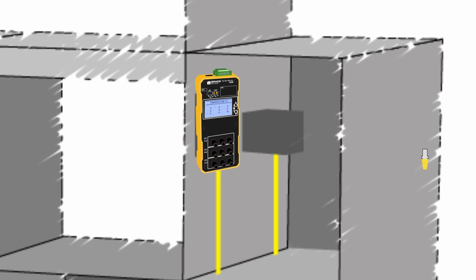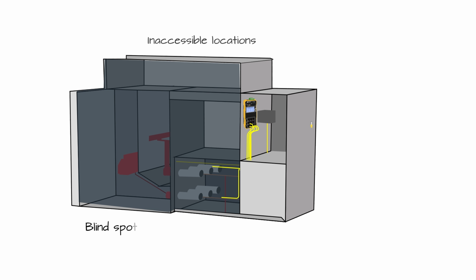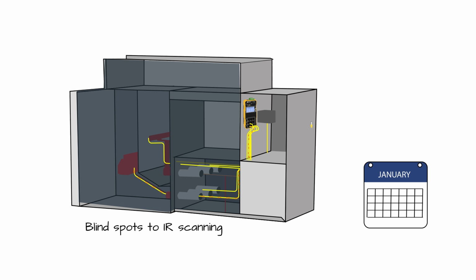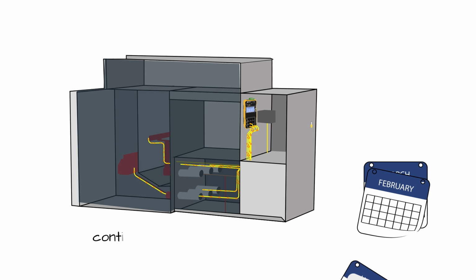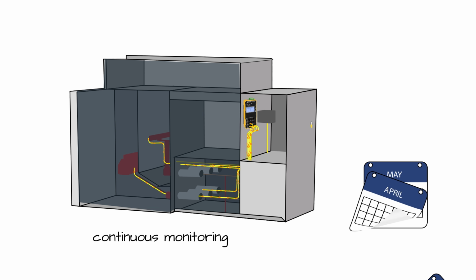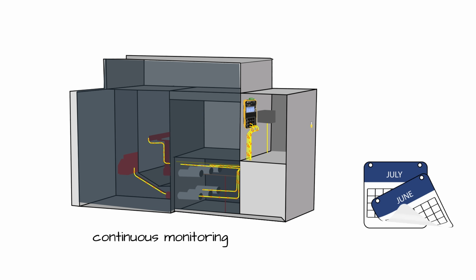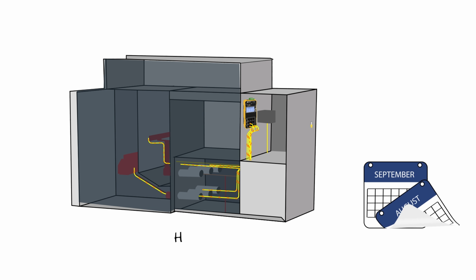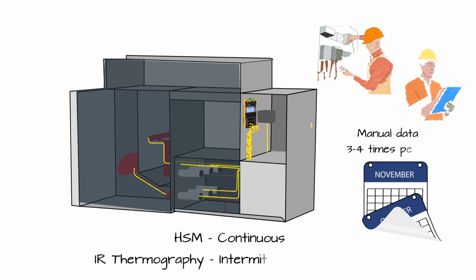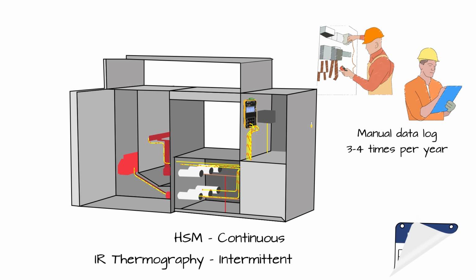Sources of heat may include inaccessible equipment and blind spots to IR scanning. The most obvious benefits of the HSM over IR thermography come from the continuous real-time monitoring feature. In addition, the successfully proven measurement accuracy of the probes is not subject to calibration errors, as can be the case with IR scans.